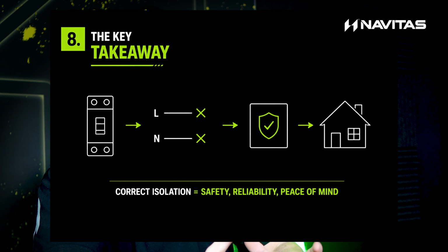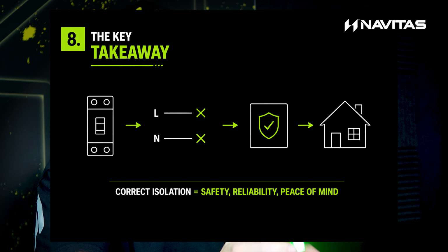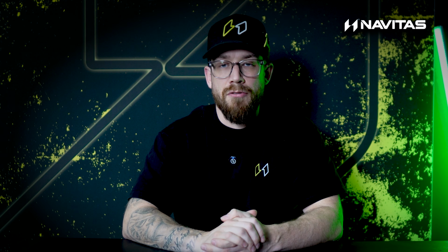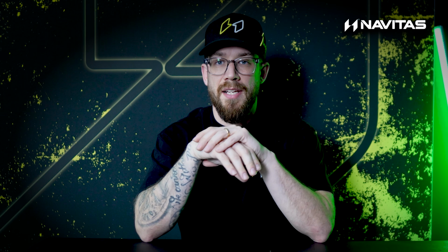And this is why we would recommend our compact RCBO that has a switch neutral function, because it's a device that allows this circuit to be completely and fully isolated after disconnection. So BS 7671 sets out those three key points of criteria that need to be achieved. And from there, it's about choosing the right device for the installation in front of you.